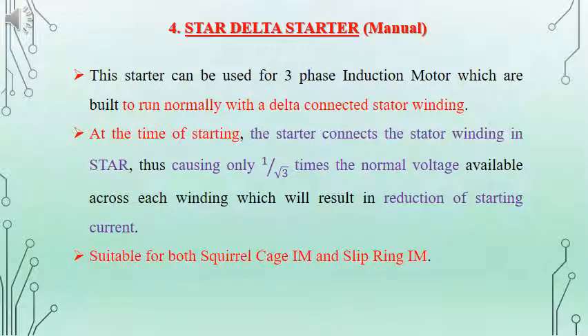Next we have the star delta starter. The star delta starter can be used for a three-phase induction motor, which is normally designed for running with a delta connected stator winding. At the time of starting, the machine will be connected in star for the stator, and later it will be converted to a delta connected system. When it is started, since it is star connected, it will apply 1 by root 3 times the normal voltage, and later the normal voltage will be applied. This can be used for both squirrel cage and slip ring induction motors.